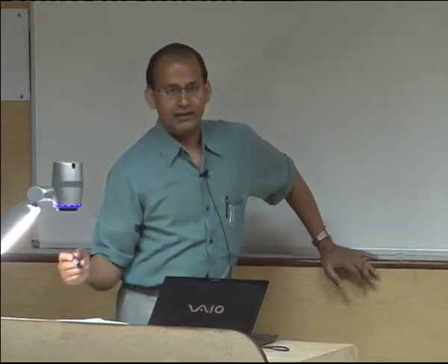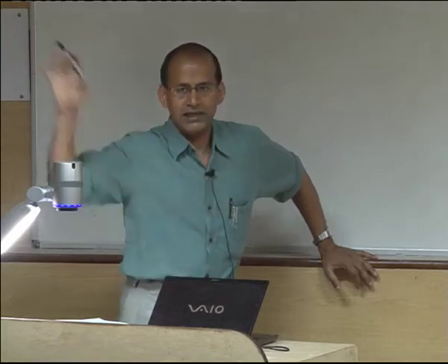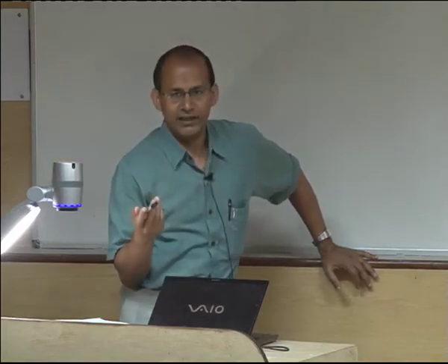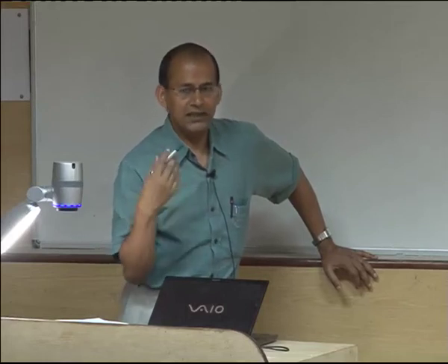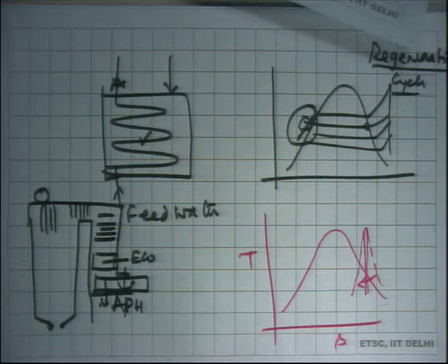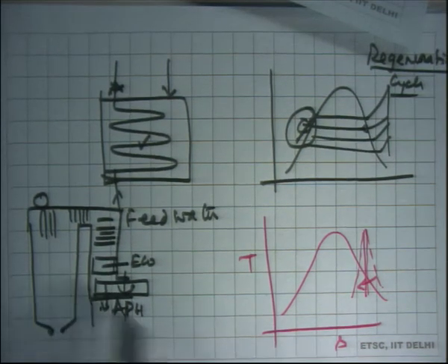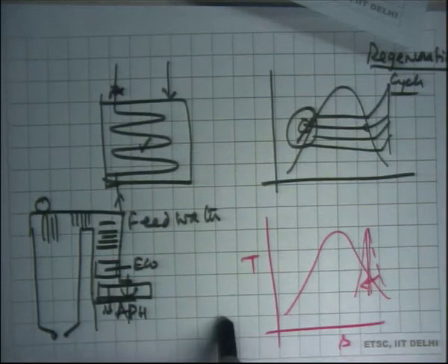The cold air for the air preheater, there are two sectors. One sector gets the cold air from the primary air fan that we saw, and the other gets it from the forced draft fan that we saw, or the secondary air fan. Okay. So, these two supply the air to the air preheater. Through the air preheater, these two air streams get heated to temperatures at which they are designed to be heated, in the process cooling down the exhaust gases even further. Okay. After this, the exhaust gases go to the electrostatic precipitator.